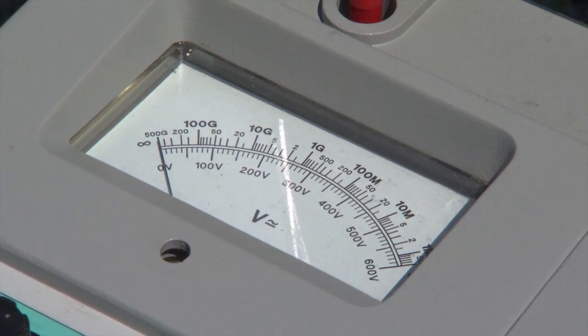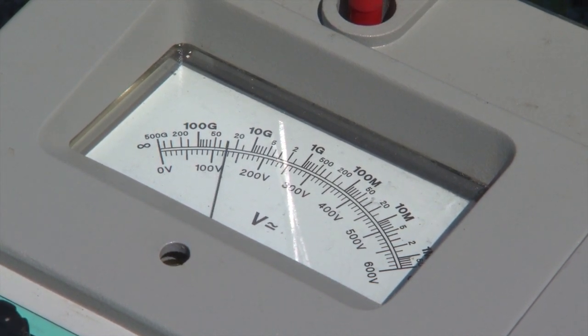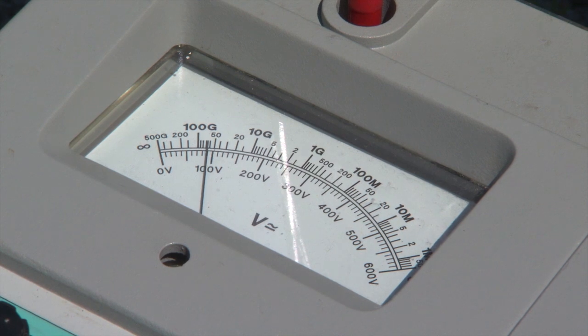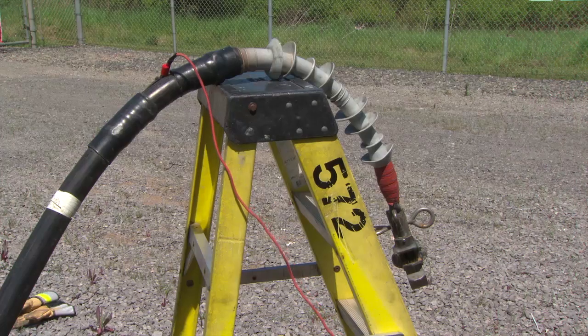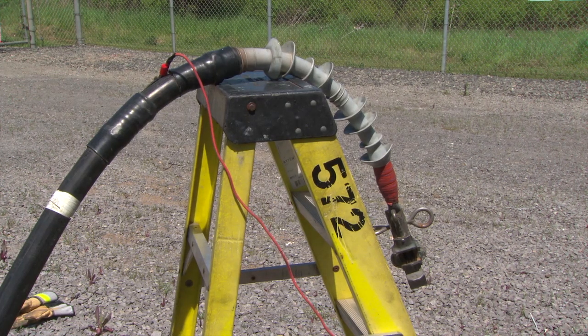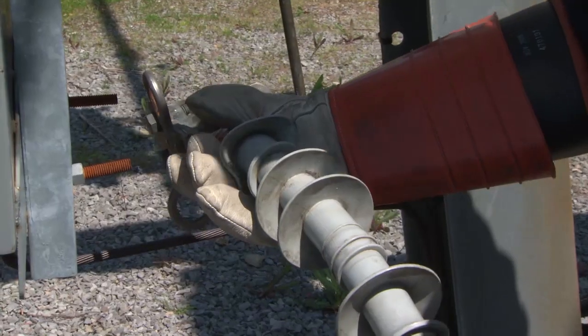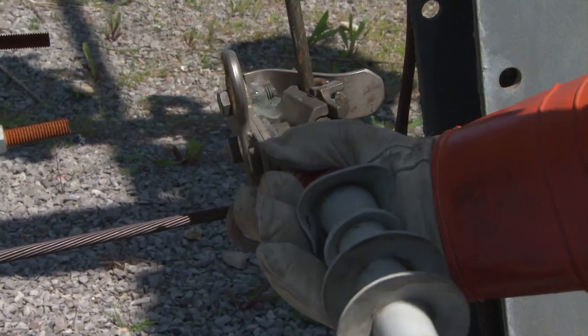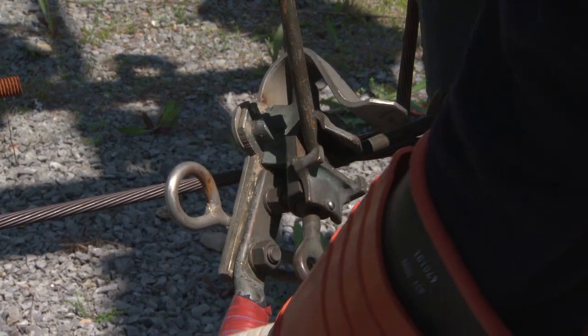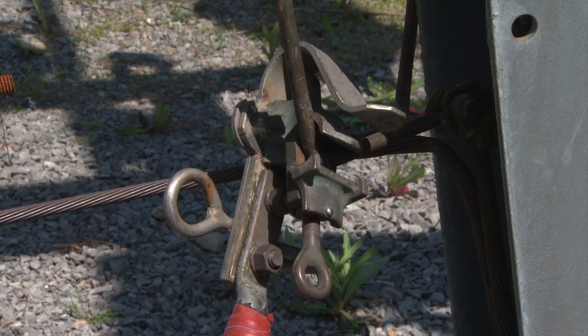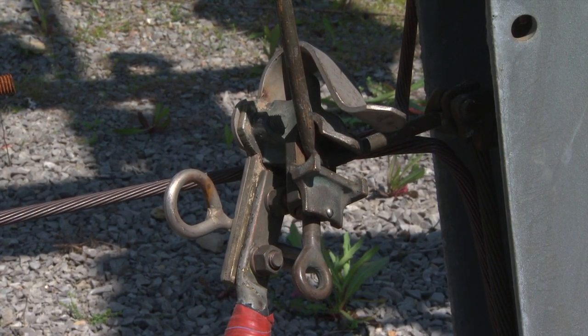If any cables are found defective, they must be tagged with a caution tag and removed from the worksite. This will eliminate the hazard of placing a defective cable in service. Once testing is complete, connect the cables to ground to drain the capacitive charge and ensure they are placed in a convenient location. No low-voltage cables are connected until the reclosers have been proven open.